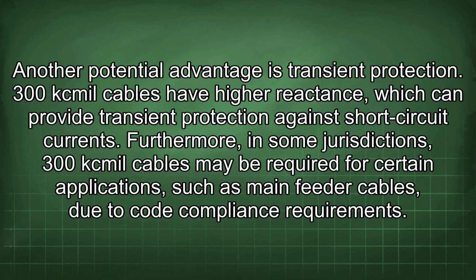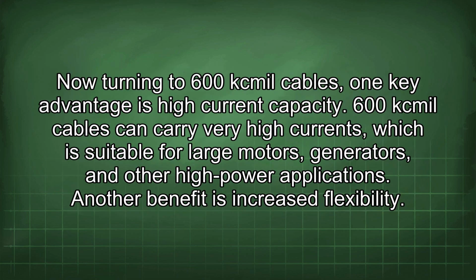Another potential advantage is transient protection. 300kcmil cables have higher reactance, which can provide transient protection against short-circuit currents. Furthermore, in some jurisdictions, 300kcmil cables may be required for certain applications, such as main feeder cables, due to code compliance requirements. Now turning to 600kcmil cables, one key advantage is high current capacity.